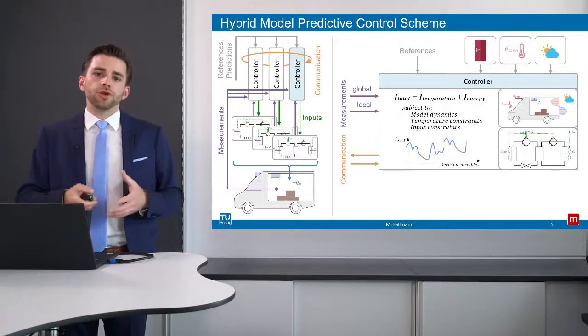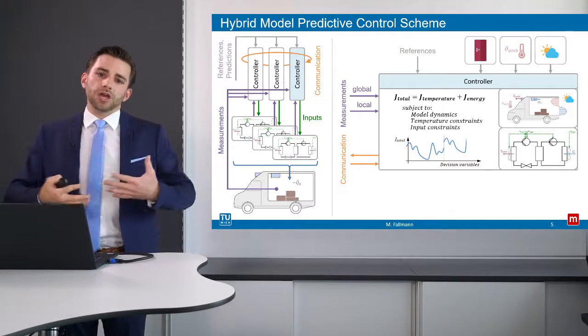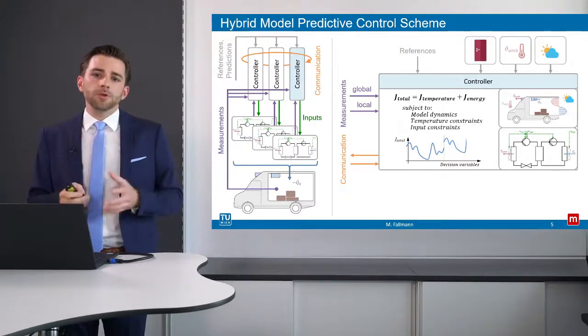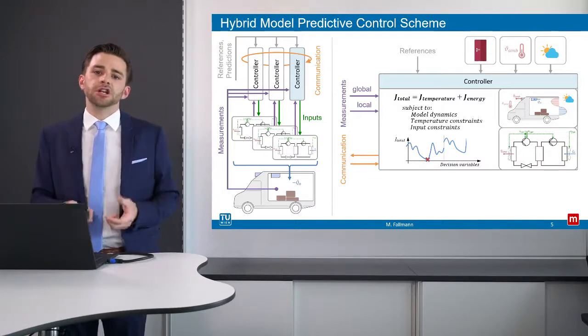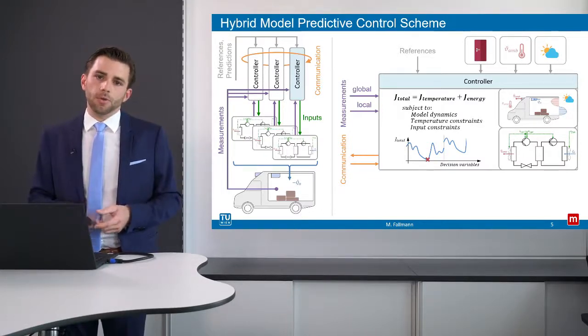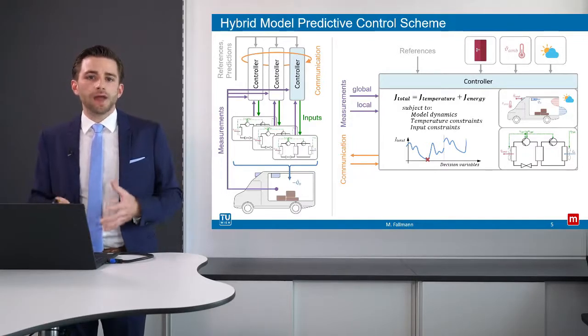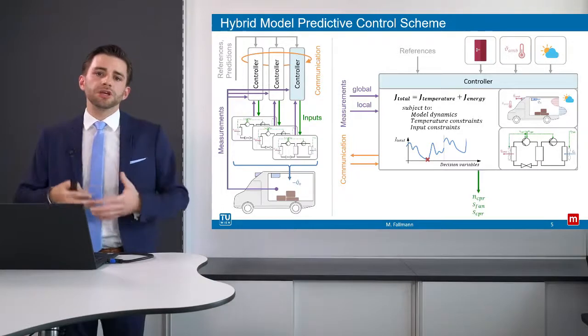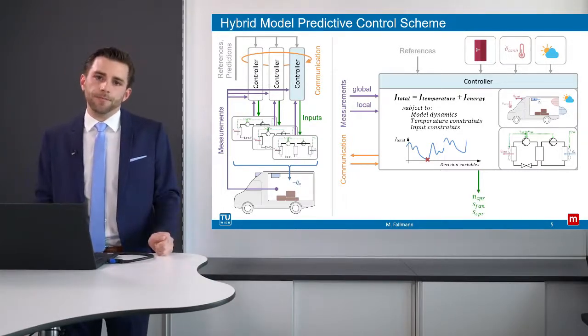And because we have used an appropriate communication strategy, we are able to find a solution that is at or at least sufficiently close to an optimal one. After finding such a solution, we can now apply values for the compressor speed, the fan switch and the compressor switch to our cooling units.